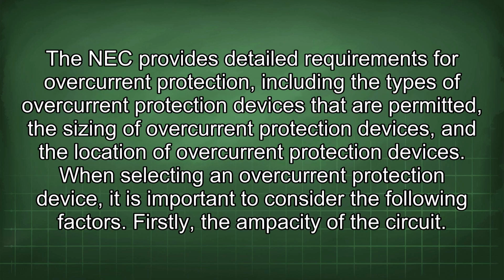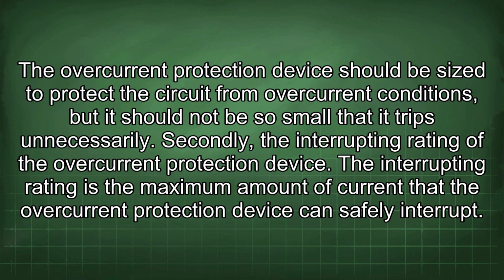The NEC provides detailed requirements for overcurrent protection, including the types of overcurrent protection devices that are permitted, the sizing of overcurrent protection devices, and the location of overcurrent protection devices. When selecting an overcurrent protection device, it is important to consider the following factors. Firstly, the ampacity of the circuit. The overcurrent protection device should be sized to protect the circuit from overcurrent conditions, but it should not be so small that it trips unnecessarily.